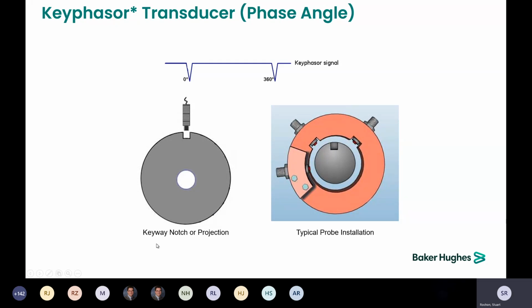We usually use a notch because a notch is the easiest one to deal with. You have the greatest chance of gapping the probe against a surface that is appropriate without having to get in there and actually look for the physical notch being not lined up with the proximity probe. I have had numerous cases where, just pure bad luck, they did get the probe lined up with the notch, gapped it, but they gapped it at the bottom of the notch, and as soon as they started the machine up, it broke the tip off the probe, and it required replacement.